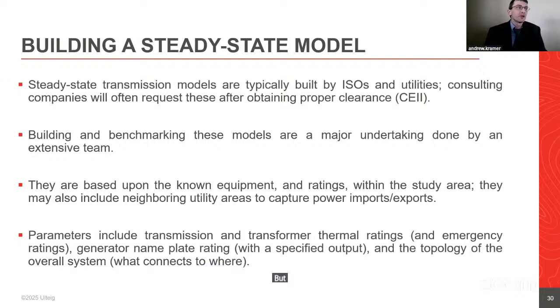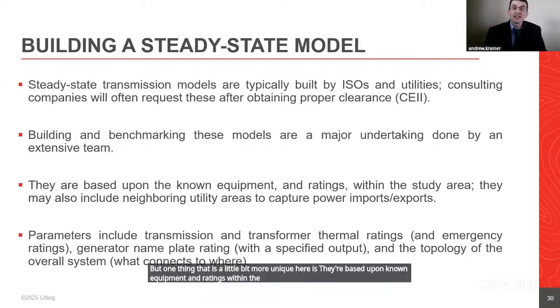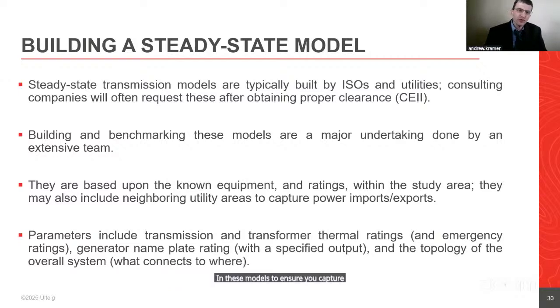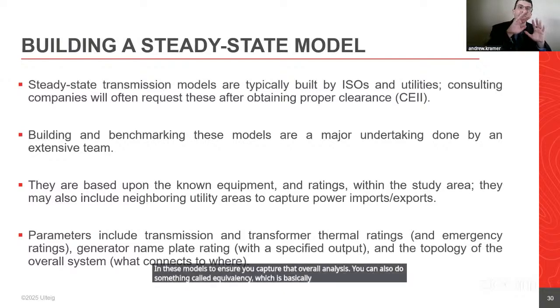One thing that's a little more unique here is these models are based upon known equipment and ratings within the study area, and they often bring in neighboring utilities. How big you want to make it is kind of up to you. When you're talking about the interface from MISO to PJM, you might go quite a few buses into PJM to ensure you capture the overall analysis. You can also do something called equivalency, where you treat the outside area as a bubble, sort of a mesh. But good practice, at least from my experience, is to include quite a few buses when going from MISO to PJM. Feel free to jump in if you think I'm misspeaking here.